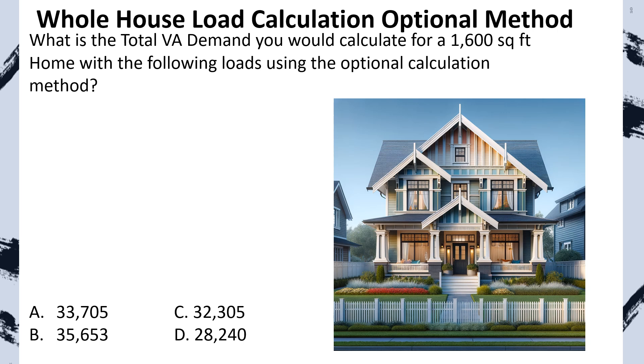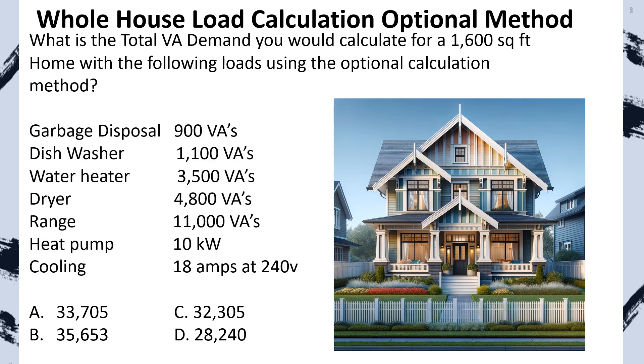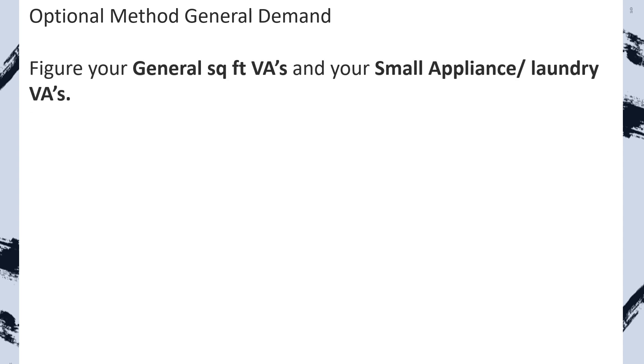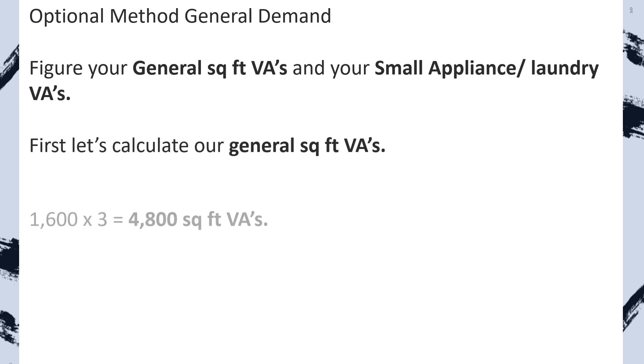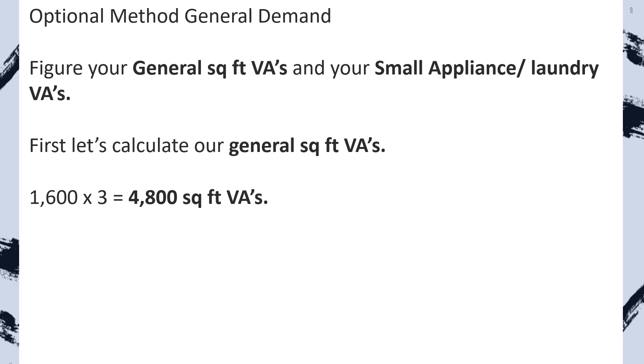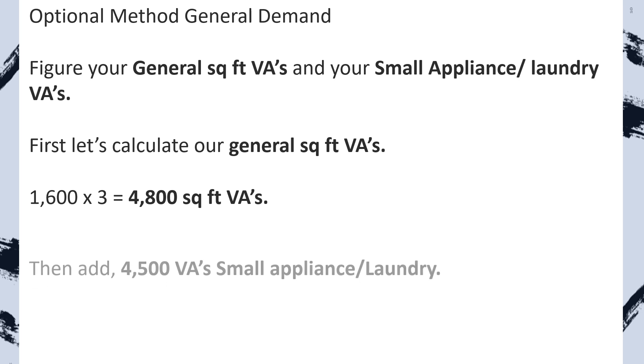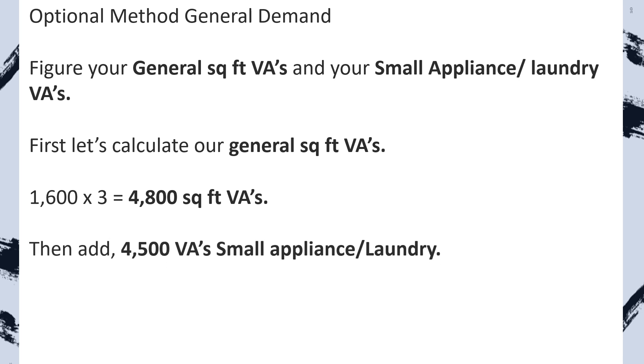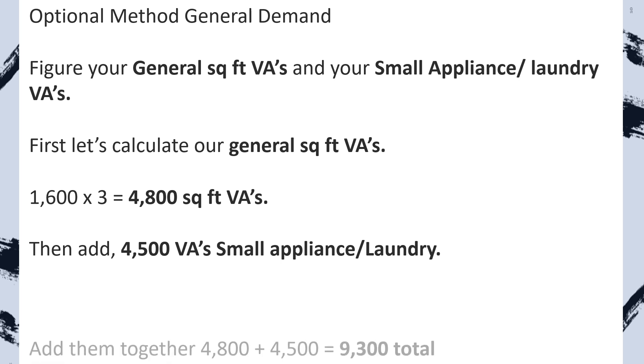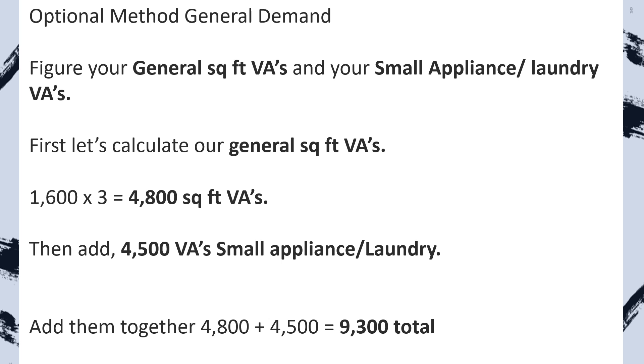What is the total VA demand for a 1,600 square foot home using the optional method? Take a minute to write down the loads so you can follow along — it's very similar to our standard method question but will go much smoother and quicker. Step one: get our general lighting demand. Take 1,600 square feet times three VAs per square foot equals 4,800 VAs, then add 4,500 for the two small appliance and one laundry circuits and total them up. We do not apply any demand factors at this point — a general demand factor comes later.